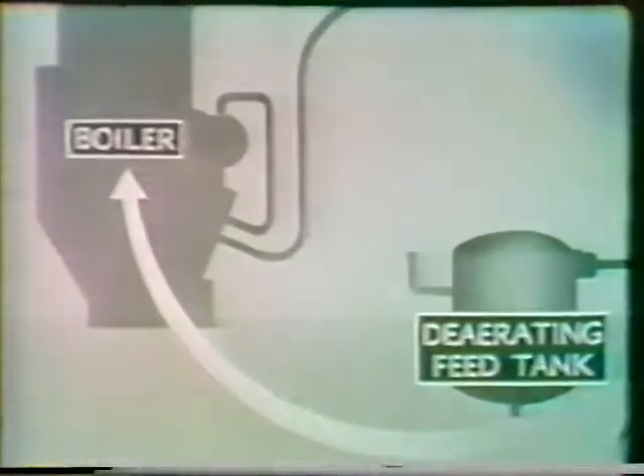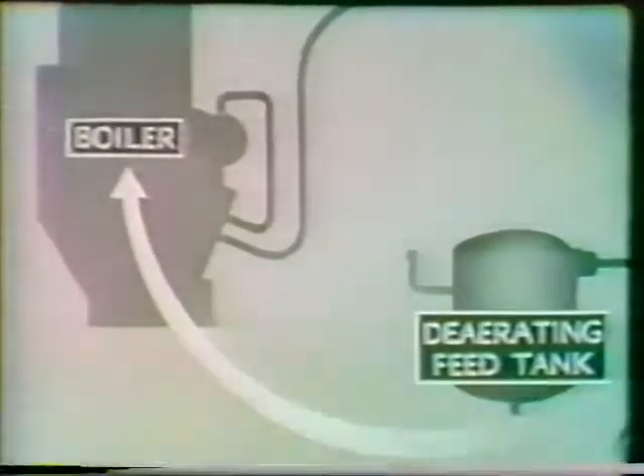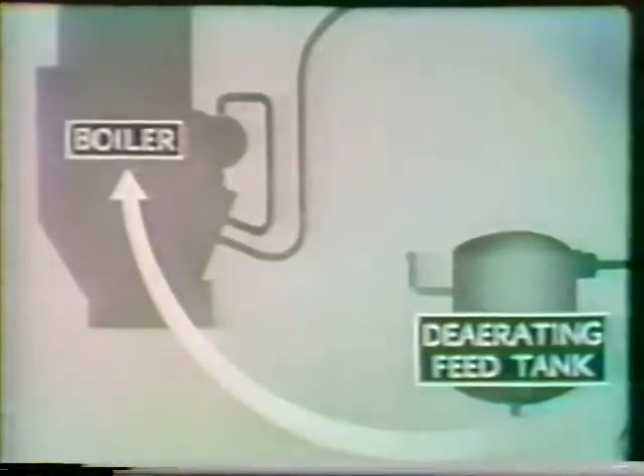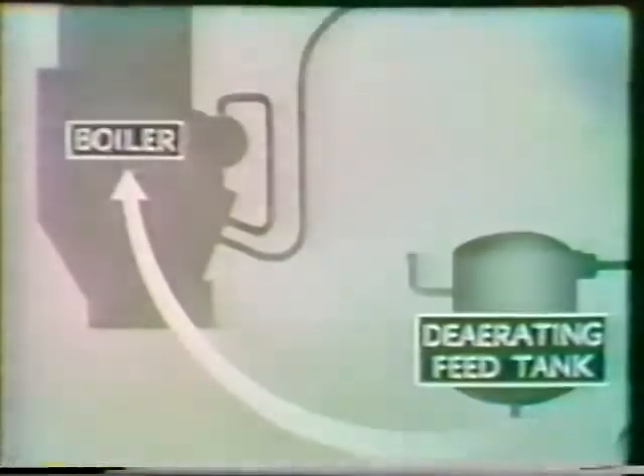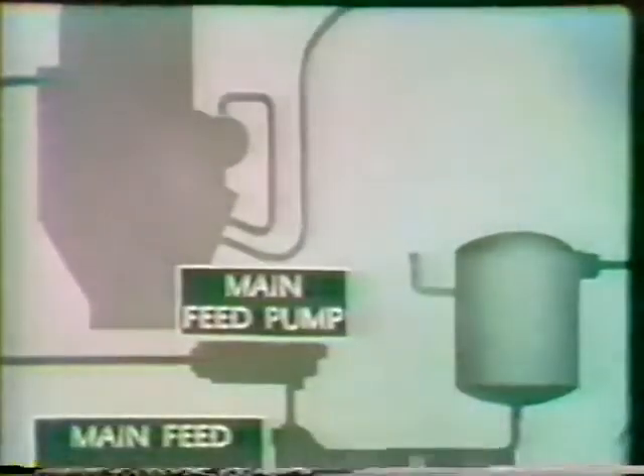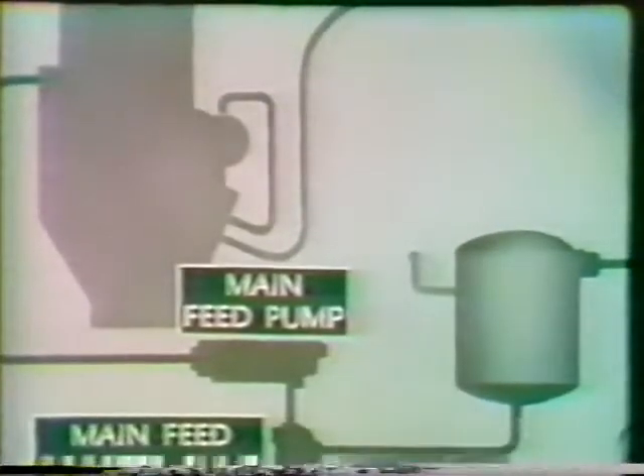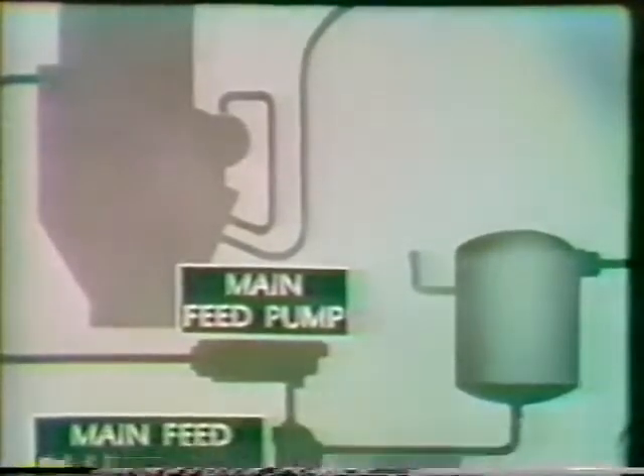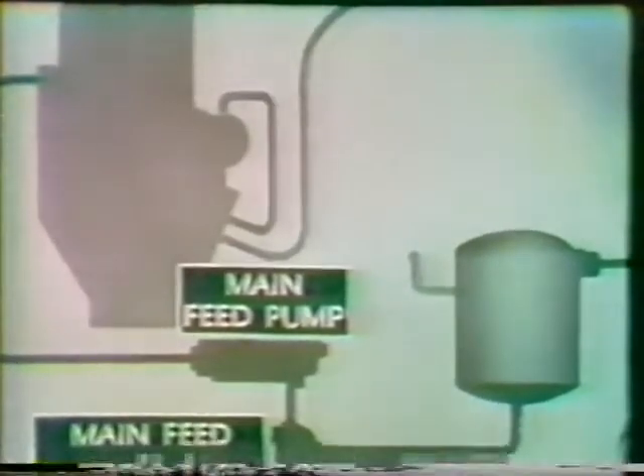Pressure and temperature are raised step by step through feed and generation, just as they are lowered step by step through expansion and condensation. Two pumps, the main feed booster pump and the main feed pump, both working on the centrifugal principle, are used to push up the pressure in stages from the low pressure level in the feed tank to the high pressure level in the boiler.